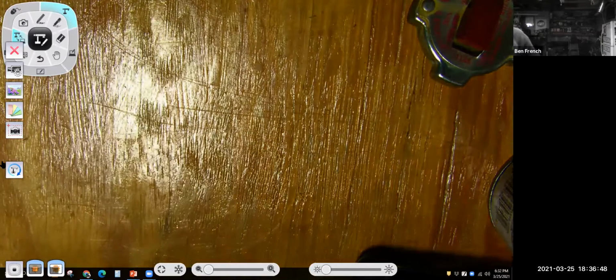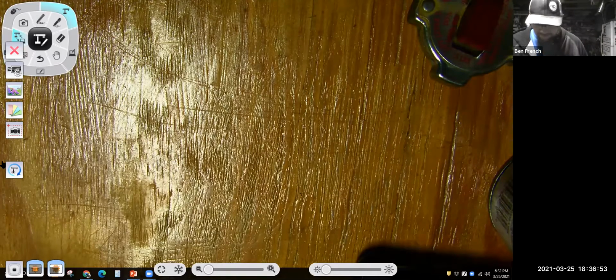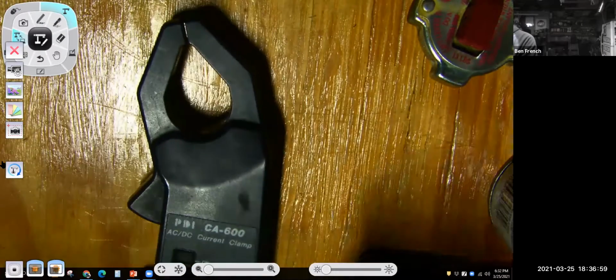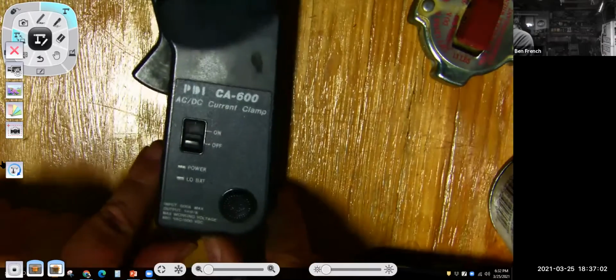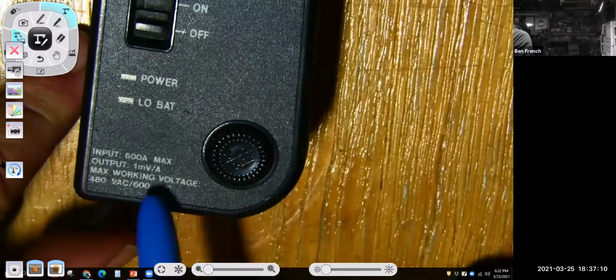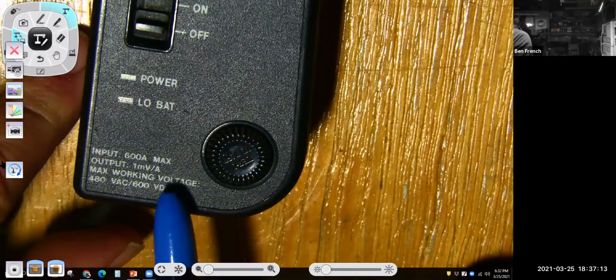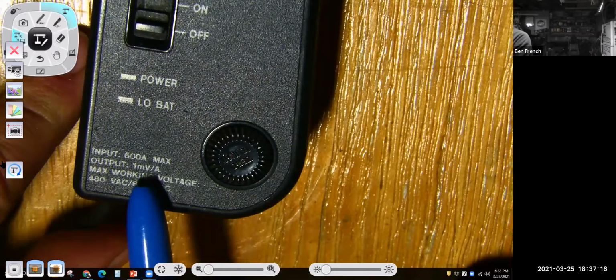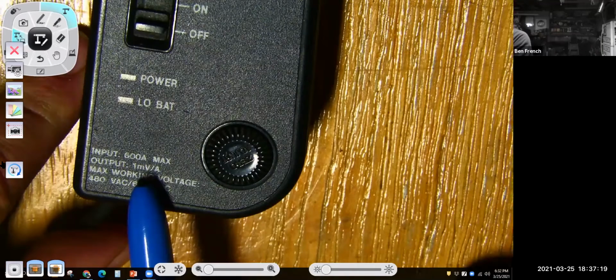Different current clamps have different scales. This other one goes up to 600 amps, so it's got a big clamp on it made to go around a big fat battery cable. The scale on this one, if I zoom in, shows 1 amp equals 1 millivolt. So if my meter says 1 millivolt, that really means there's 1 amp flowing around whatever cable you put it on.